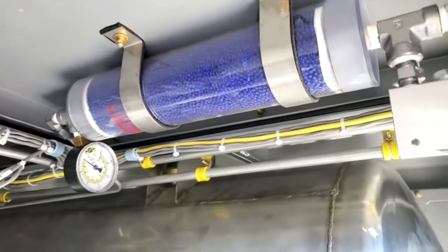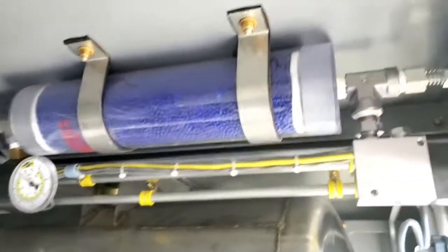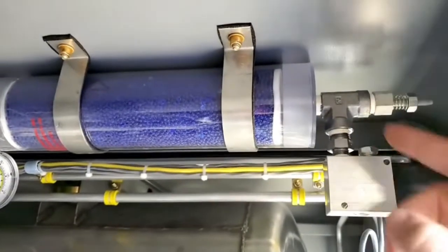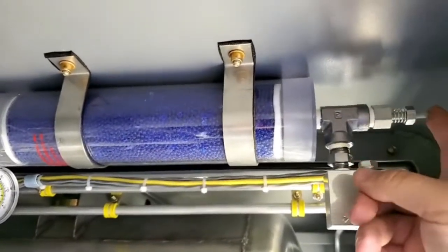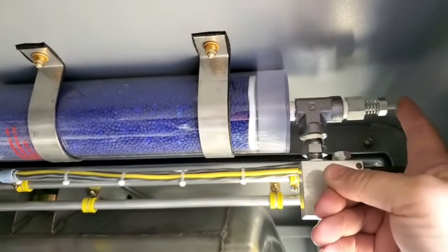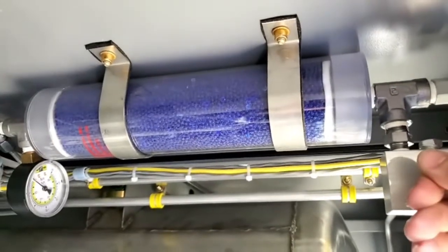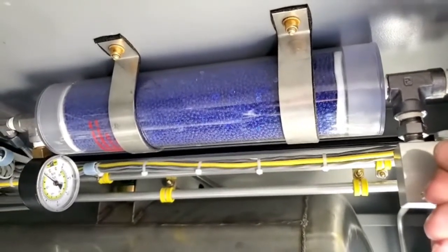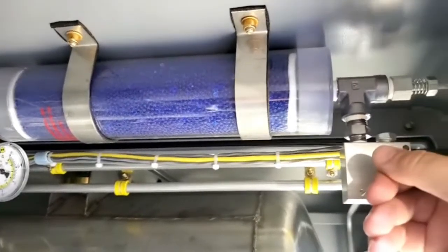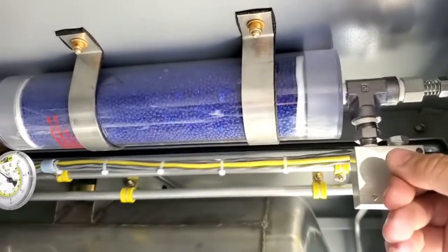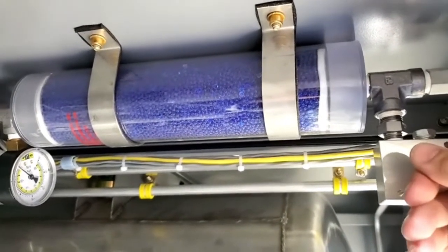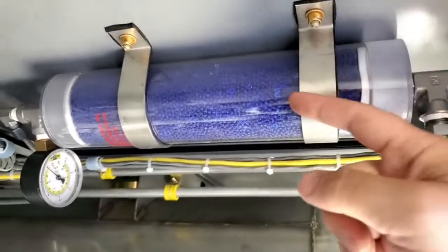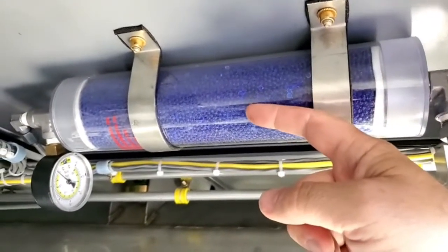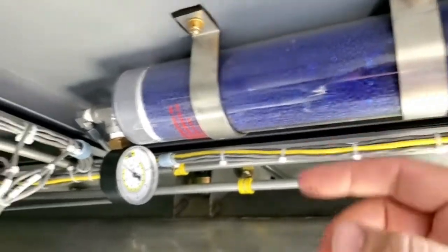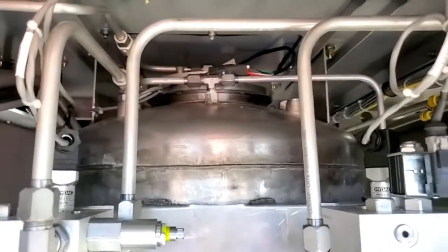Now this gauge is connected to the desiccant filter. There's a spring-loaded relief switch right here, which prevents the tank from being drawn into too heavy of a vacuum. Anytime this spring opens to allow air in and maintain the vacuum, the ambient air passes through these silica beads, which draw the moisture out of the air, so you have dry air going into the tank to maintain your vacuum.